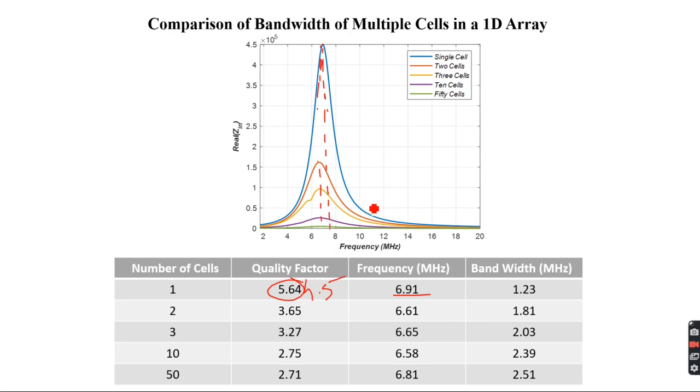The shift of frequency, again, I can put this blame on the effect of the mutual acoustic crosstalk, but it also depends on the aperture size of the CMUT. How does it compare with the wavelength, right? How much the aperture size compares with the wavelength.